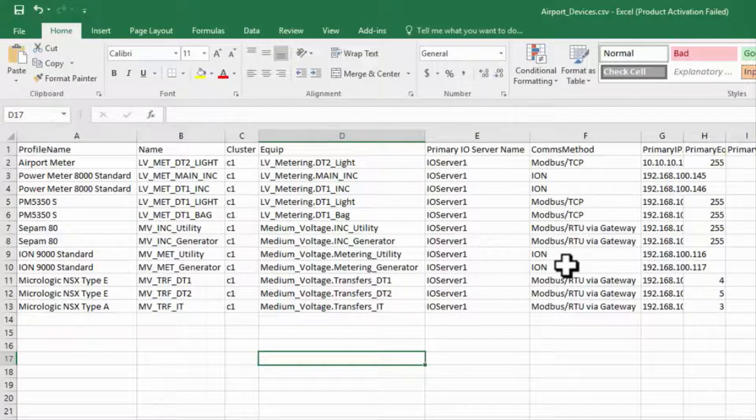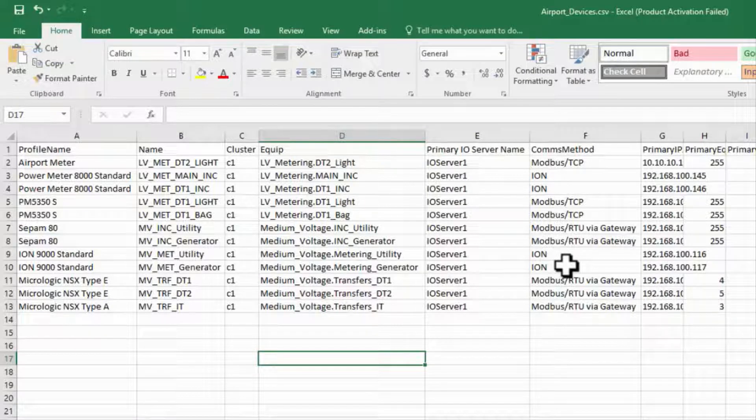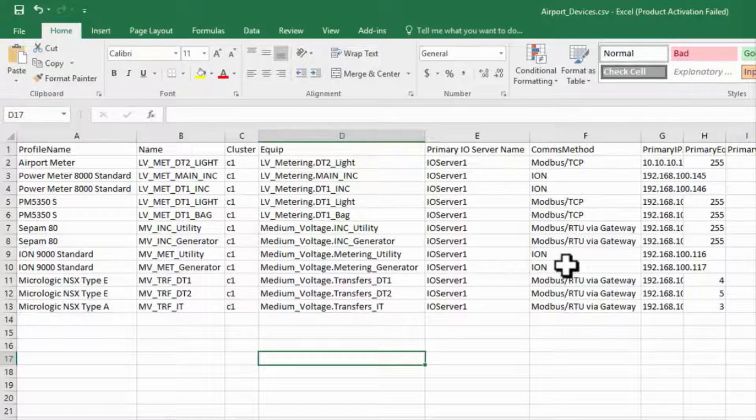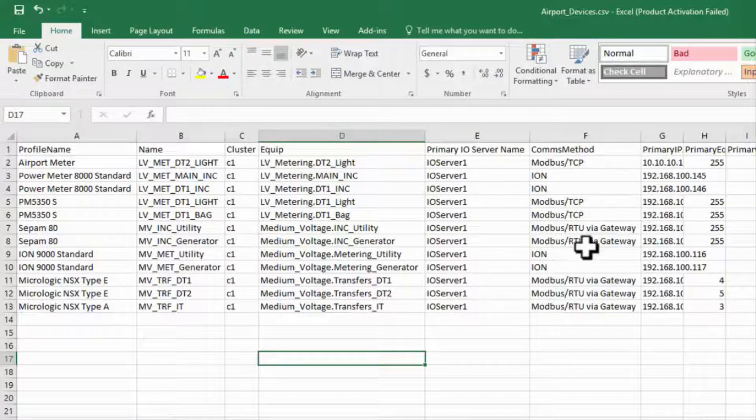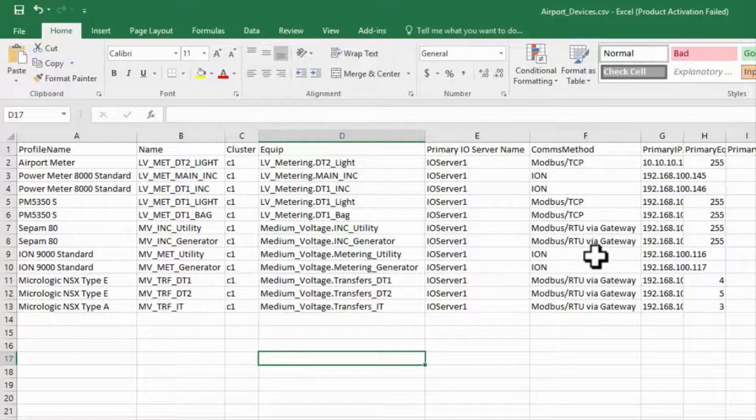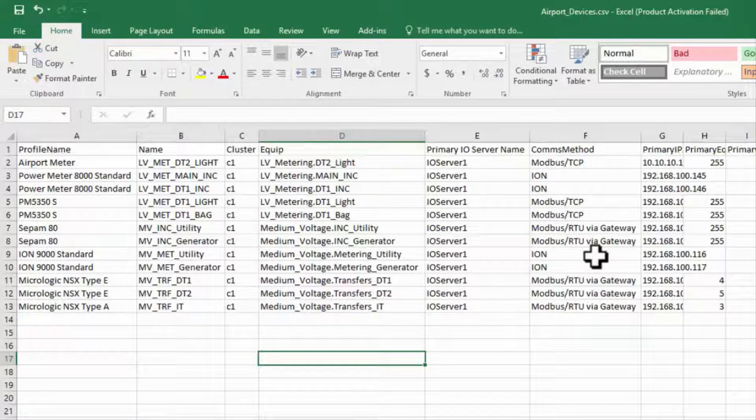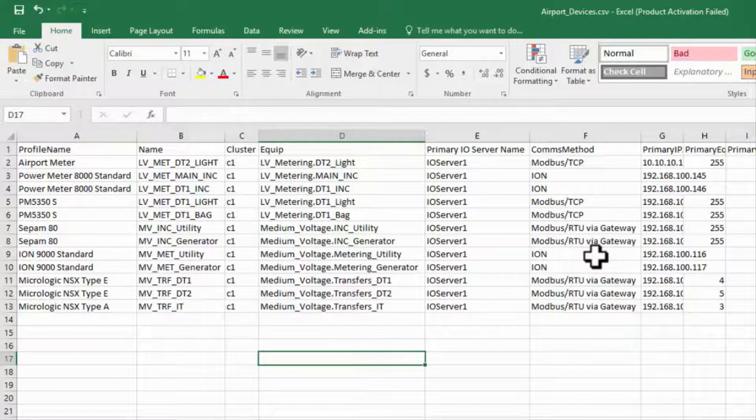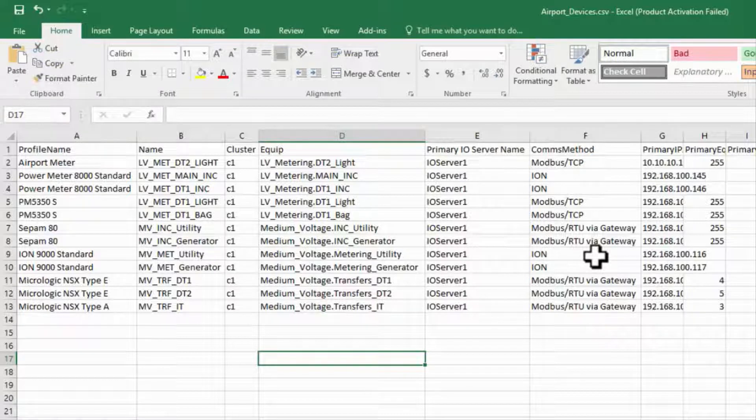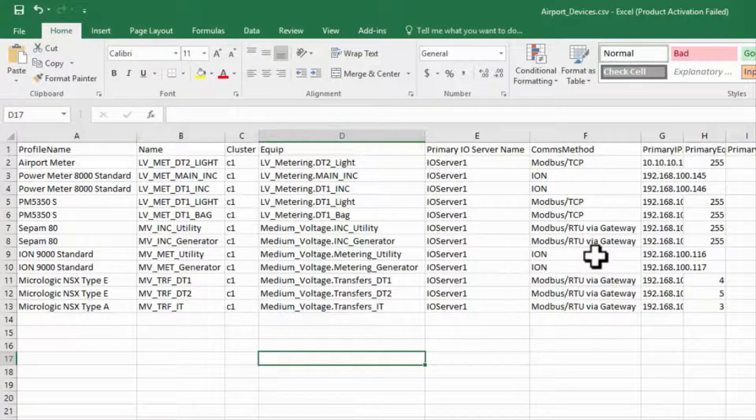Other protocols do not specify a standard location for waveforms, so we are limited to what has been explicitly programmed in the drivers. That is to say, the Power Modbus driver can gather waveform data from compatible Schneider Electric Modbus devices like the CM4000, PM800, and MicroLogic Type H. However, this is not available to just any Modbus device, only those that the developers have enabled it for.